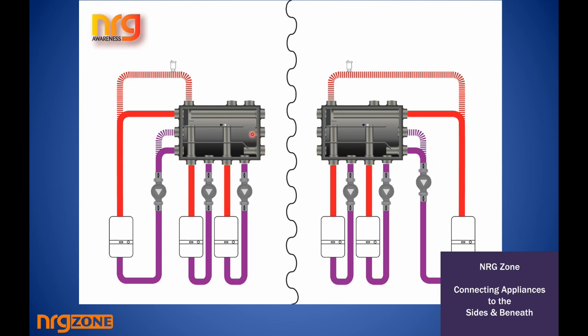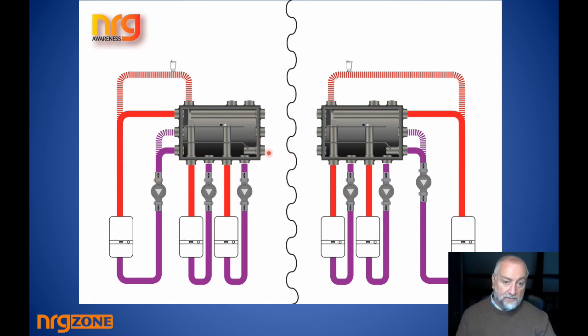So you could in effect have, let's say, a 28 mil pipe here, 28 mil pipe here, and because it's such a short distance, go up to even a 50 mil pipe here and take away the heat from 3 or 4 boilers, if the pipe capacity and the resistances that you calculate are able to do the job. So just because you have inch connections, you can combine the connections and take much more heat. Same thing applies on the right hand side.